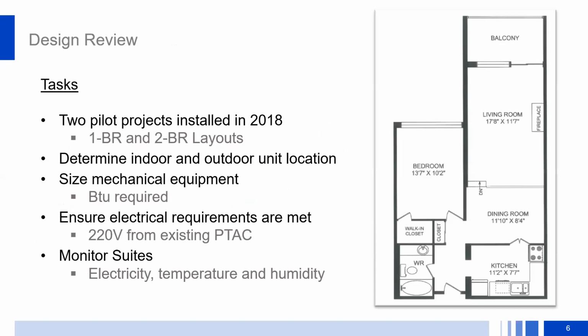To begin with the pilot projects, it's been just over 2 years since we started with a 1-bedroom and a 2-bedroom layout. To do this, we had to determine the indoor and outdoor unit locations, as well as their sizing, and figure out how many tons we'd need. For electrical, luckily the PTAC units had a 220 connection, so we could use that for the full electrical needs. The goal with the pilot projects was to get about a year's worth of data on electricity, indoor and outdoor temperature, and humidity, to make sure these units would really do what we thought they were supposed to do. Next slide, please.